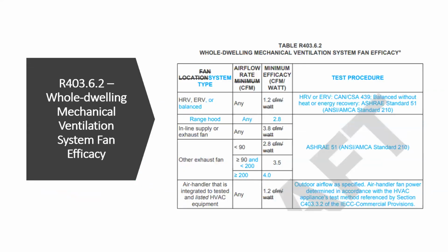So also a change a little bit into a table is the whole dwelling mechanical ventilation fan efficacy. There was always just this short little version of a fan efficacy table, but now they've made some adjustments here. They took out location, they just say system type. They don't say the airflow is a minimum. They actually look at it as a starting point. It's not just minimum, it's a starting point and goes up. And then of course you've got that CFM per watt as well.